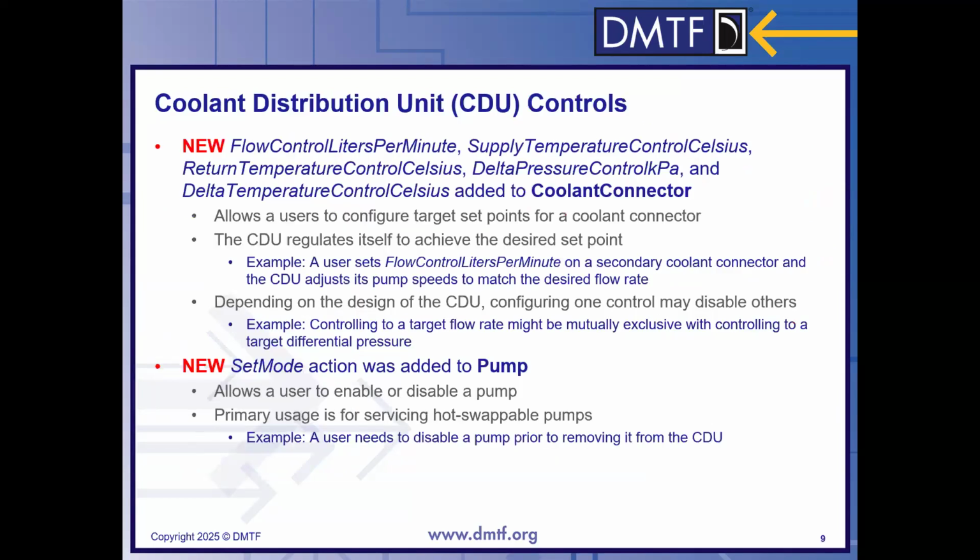Mike? All right. Thank you, Jeff. So, as Jeff already indicated, one of the big pieces we added for this release was standardizing on several of the control mechanisms for coolant distribution units. This came from direct feedback from the industry for what types of control pieces exist in existing CDUs today. These are things you might find if you go into a CDU's web interface. There might be a drop-down menu or some other form to fill out to set the different control points.